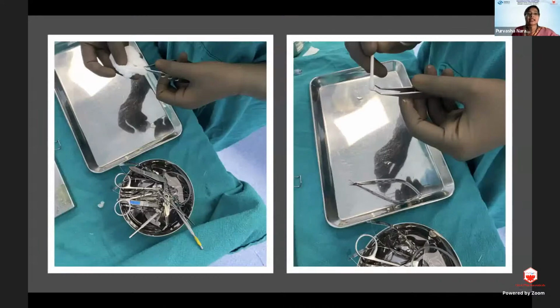So what you have to teach the circulating and scrub nurse is that proper observation and inspection of these tips has to be done, either with a moistened lint-free cloth or a piece of cloth which is sterile. All the tiny crevices, hinges and serrations have to be cleaned properly, and any inorganic or organic debris which is present has to be immediately removed. It could be in the form of viscosurgical device or visco present over the surface, which can dry up and later cause problems in sterilization. Inadequate sterilization is caused. Otherwise, blood or lens matter, any of these materials can lead to ineffective sterilization. So this has to be properly removed.